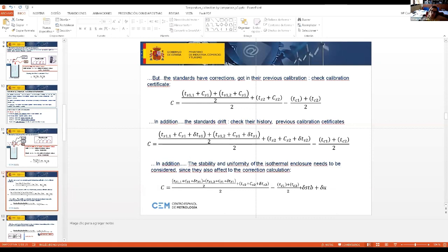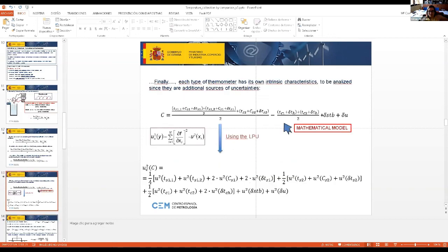But also we know that we don't have a perfect isothermal enclosure. It means it has a lack of stability and a lack of uniformity that needs to be taken into account when we calculate the correction. And finally, the thermometer under calibration has its own intrinsic characteristics, depending on the type of thermometer we are calibrating, that need to be included in the mathematical model. Here we have our complete mathematical model. Now, applying the GUM and using the law of propagation of uncertainties, here you have the uncertainty calculation related to the correction.